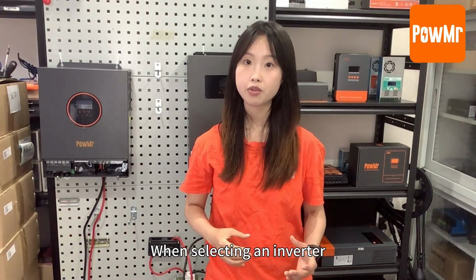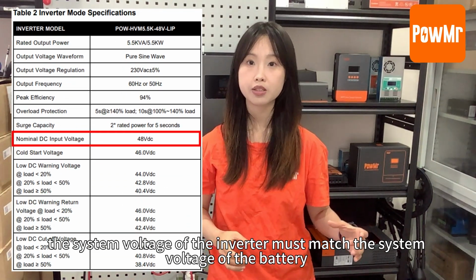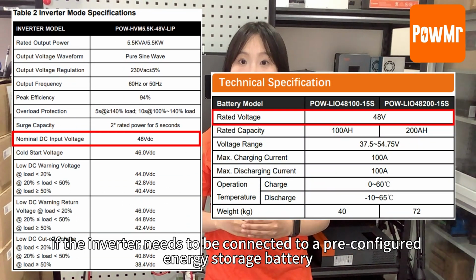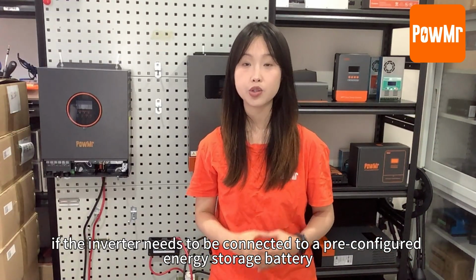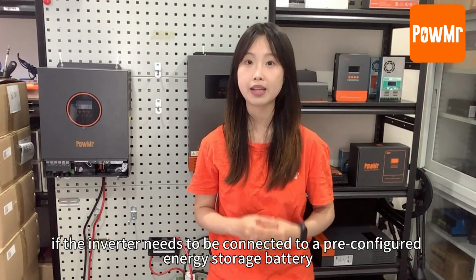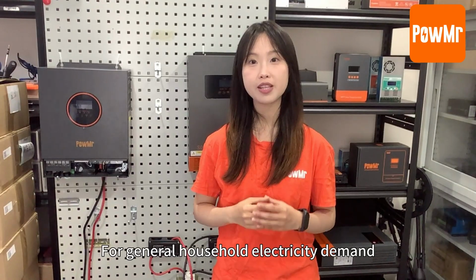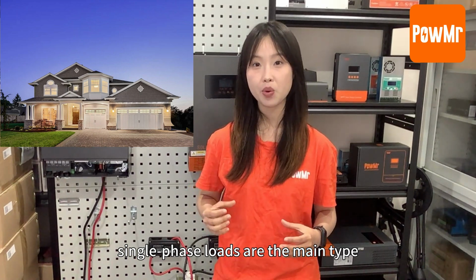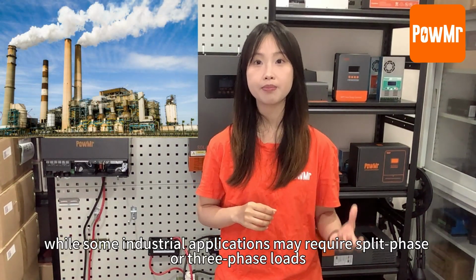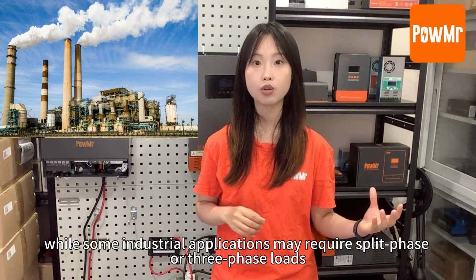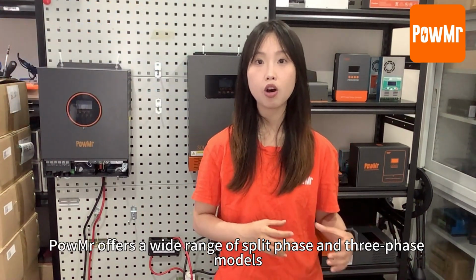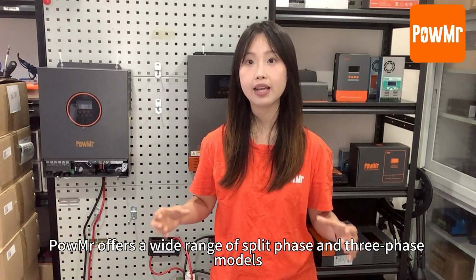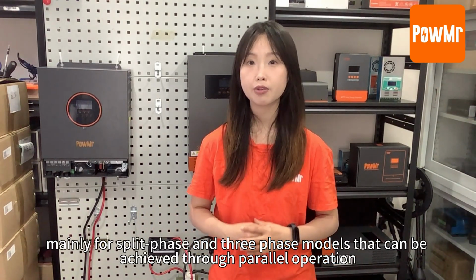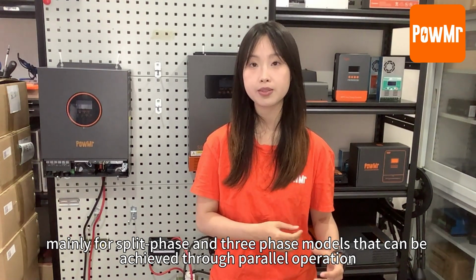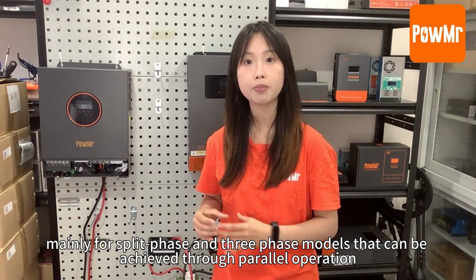When selecting an inverter, the system mode of the inverter must match the system mode of the battery, if the inverter needs to be connected to a pre-configured energy storage battery. For general household electricity demand, single-phase loads are the main type, while some industrial applications may require split-phase or three-phase loads. PowMr offers a wide range of split-phase and three-phase models, and the split-phase and three-phase models can be achieved through parallel operation.